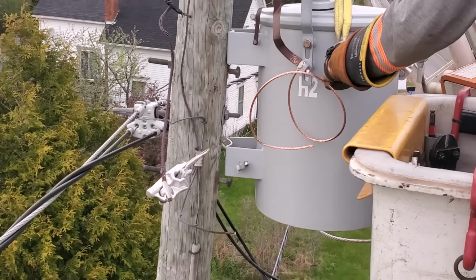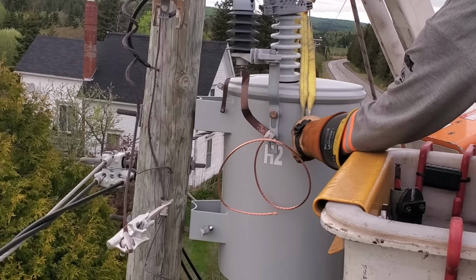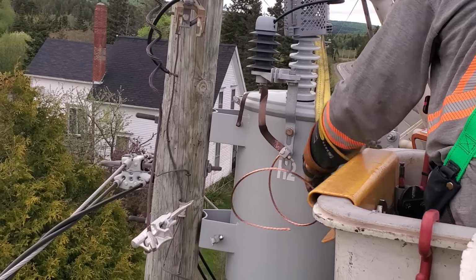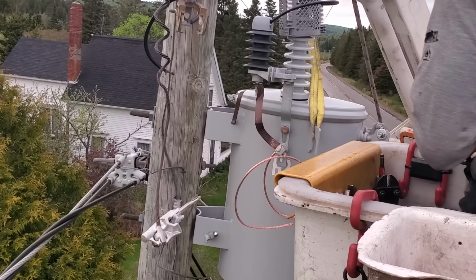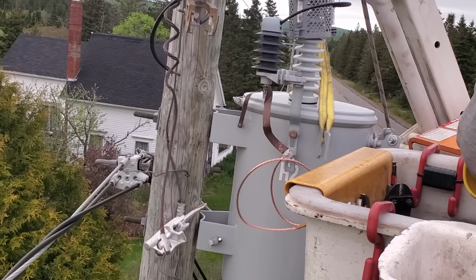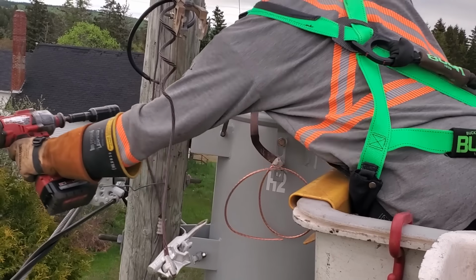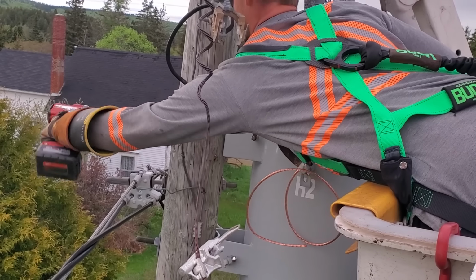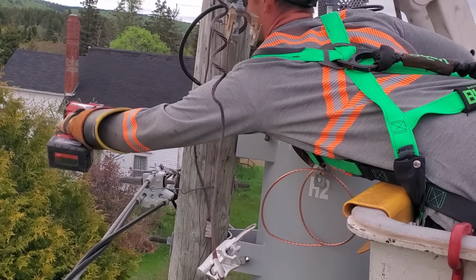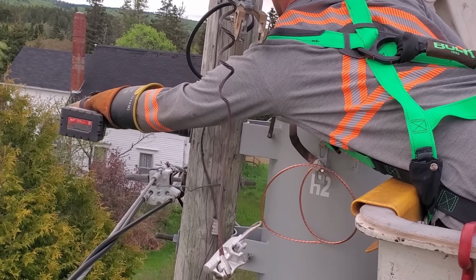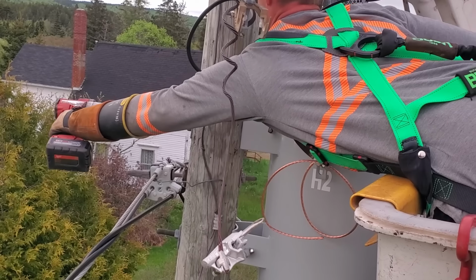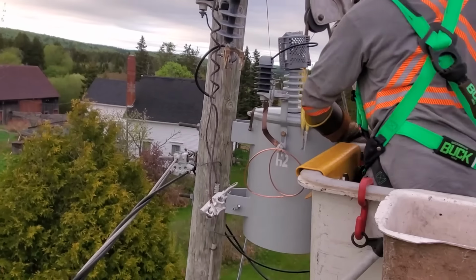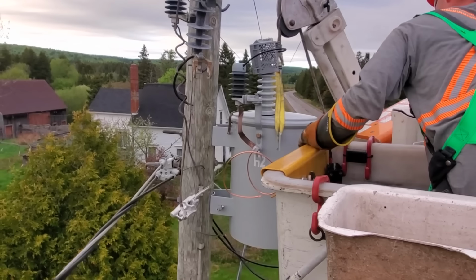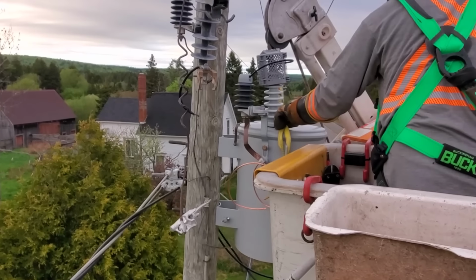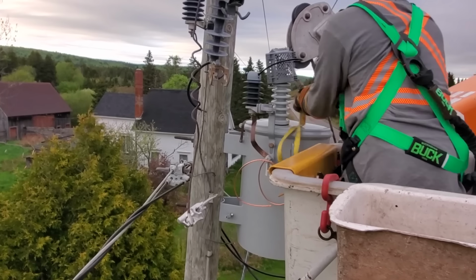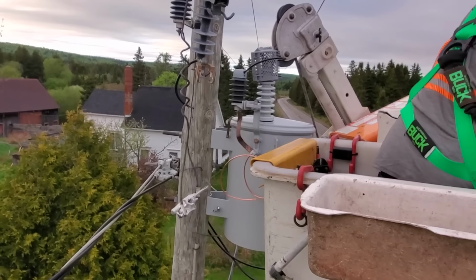So these holes were pre-drilled obviously, but very important to make sure that when you are making new construction and hanging a transformer, that the bolts top and bottom are perfectly in line, or else you'll get quite a bit of grief when you're hanging it. The newer lightning arrestor, this might get loud. As long as that top bolt's tight when hanging a transformer, you can release it in order to better position yourself to remove that, or to tighten that bottom bolt. That top bolt will hold the weight of that, no problem. The bottom one's pretty well just to stabilize it.